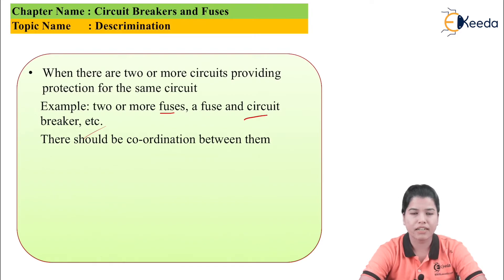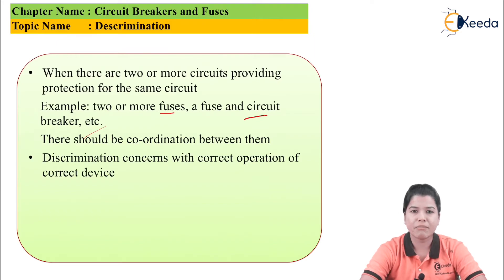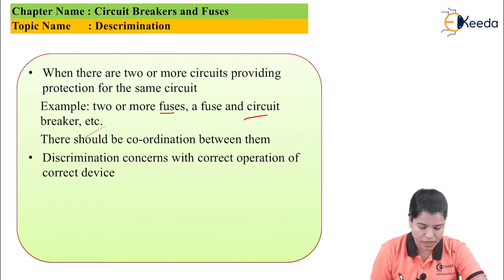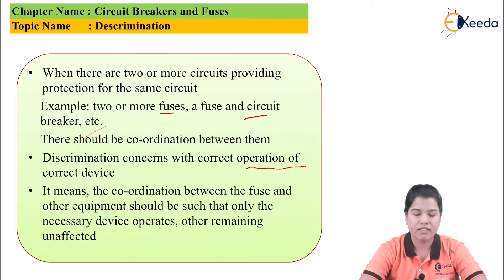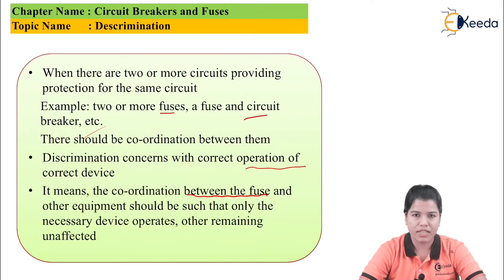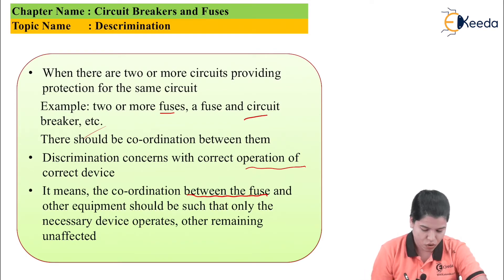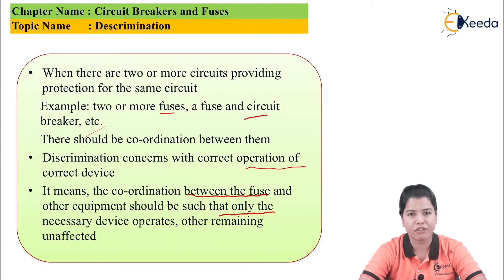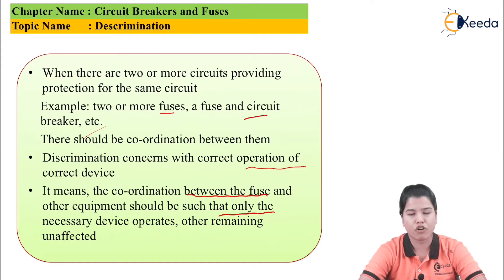Suppose a fuse and a circuit breaker are connected together. There should be proper coordination between the fuse and the circuit breaker connected for the protection of the motor. Discrimination is the property which concerns the operation of the correct device, meaning only the equipment that is necessary to protect the device should operate.